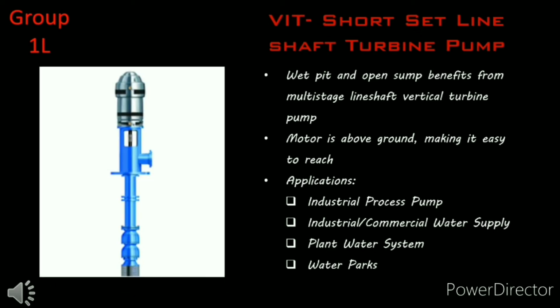The first one is the VIT, short set line shaft turbine pump. Wet pit and open sump pumps benefit from multi-stage line shaft vertical turbine pumps. The hydraulic components of line shaft vertical turbines are immersed in the pumped fluid, but the motor is above ground, making electrical components easy to reach. For applications with greater temperatures or variable fluid characteristics, this form of pump offers greater material and configuration versatility than submersible pump and motor combinations.